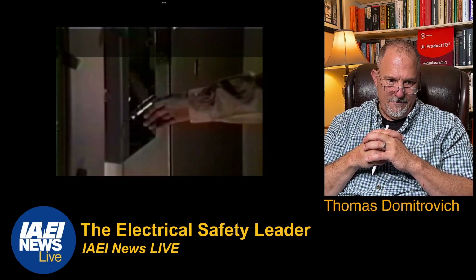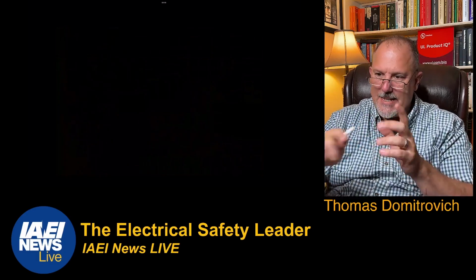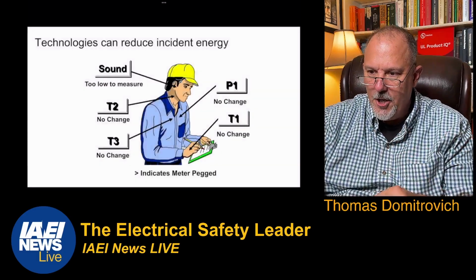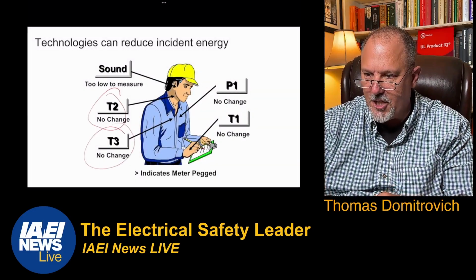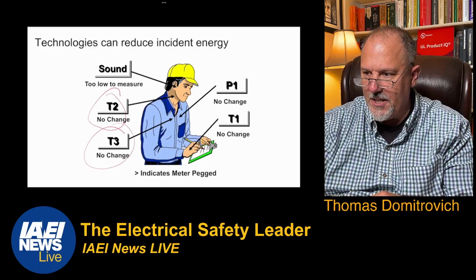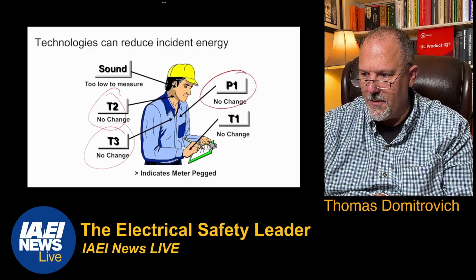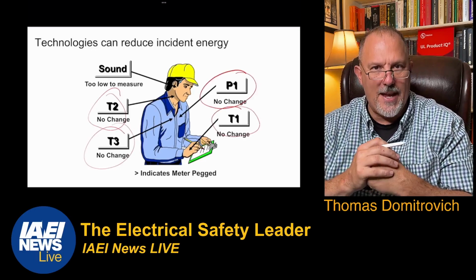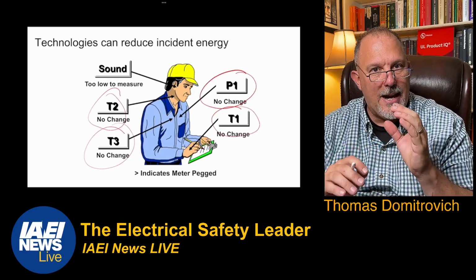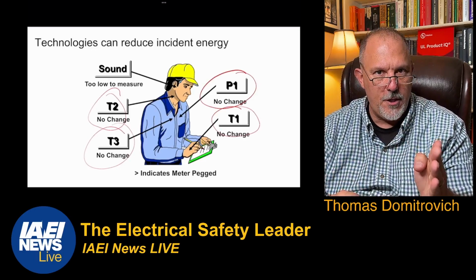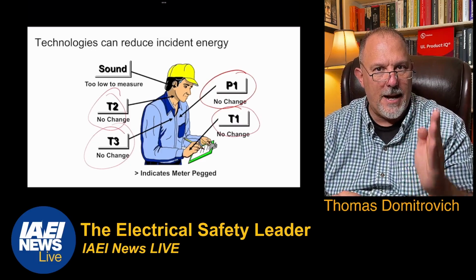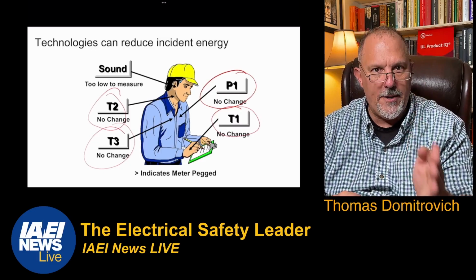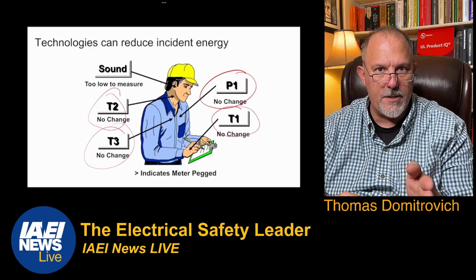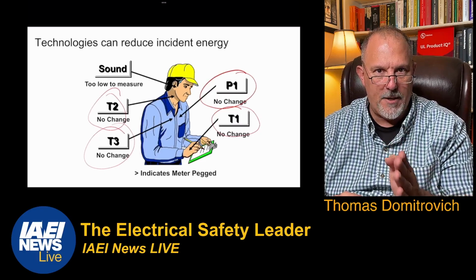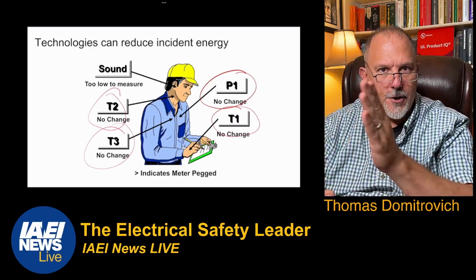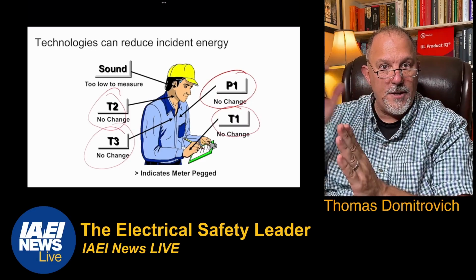And that's it. So there was no data. No change in temperature at the neck, no change in temperature on the chest, no change at pressure on the chest, and no change at temperature on the hands. Why? Because I put a smaller fuse for the exact same circuit, meaning I went in the current limiting region of the overcurrent device. Now I can have that happen by reducing the overcurrent device or increasing the fault current.